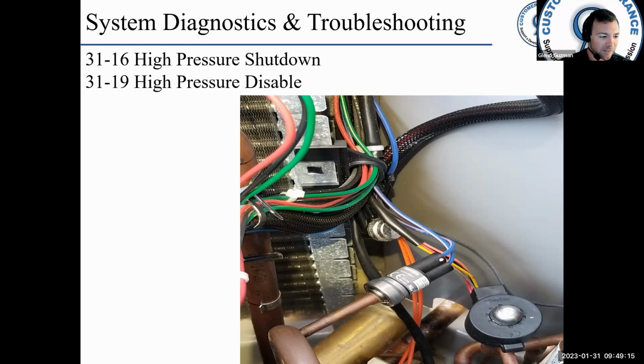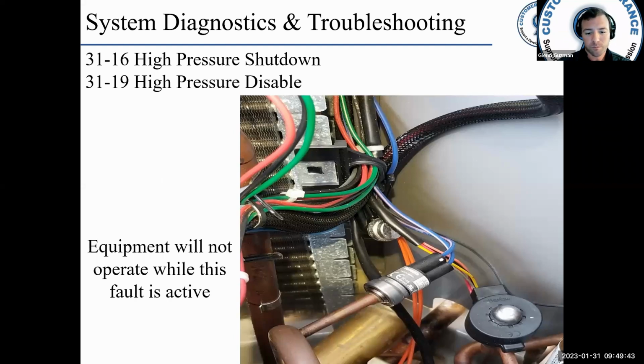If that fault is active, again, connect your gauges, see what you have, and look at the UI, look at the app, see what it thinks you have. You could have a problem with the transducer. You could have an issue with the pressure equalizing valve. Remember, pressure equalizing valve should be opening before and after a cycle. So those are some things to check. The equipment will not operate while this fault is active.